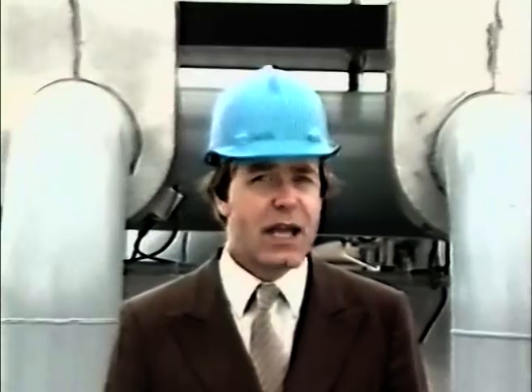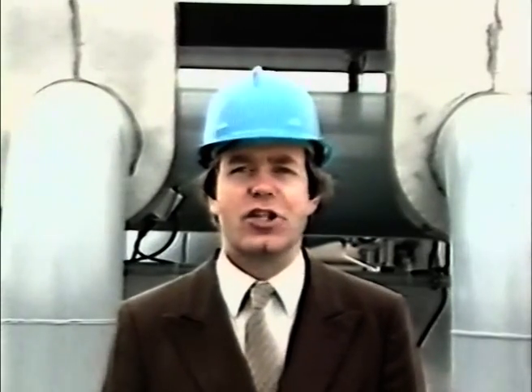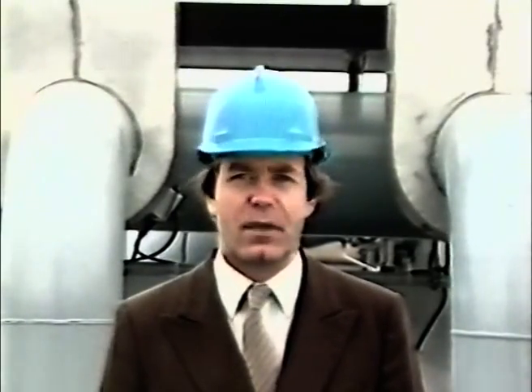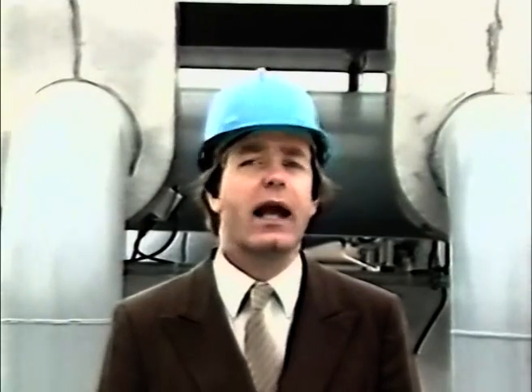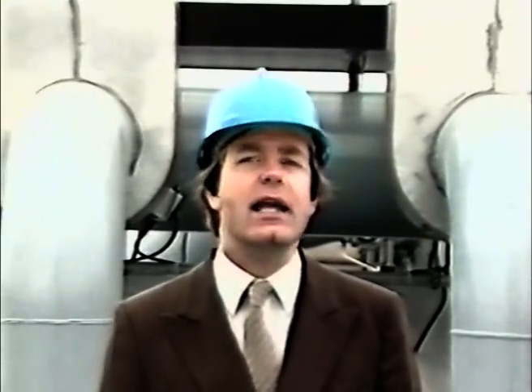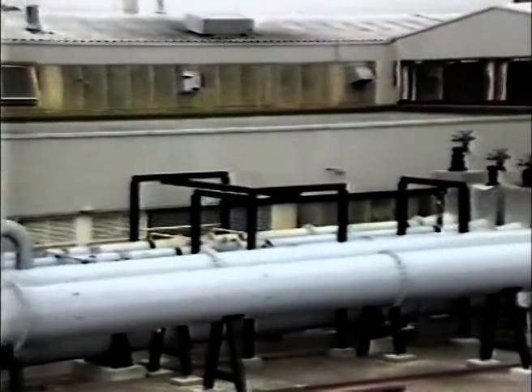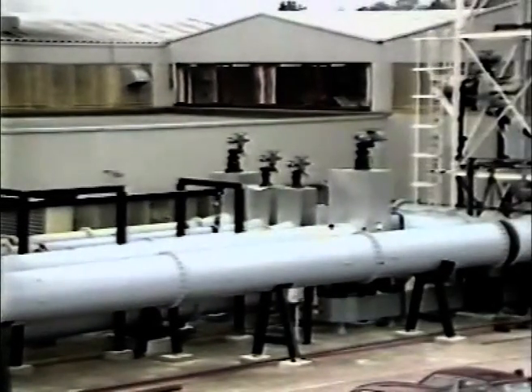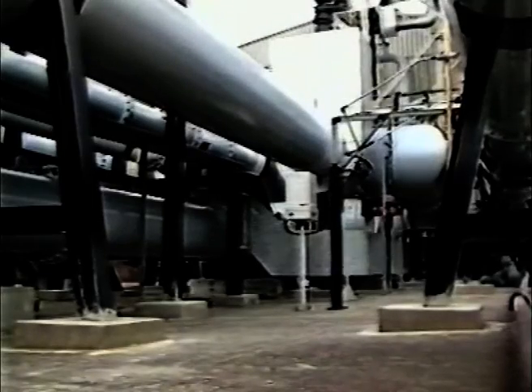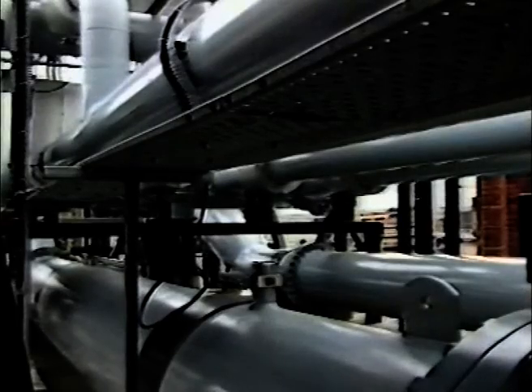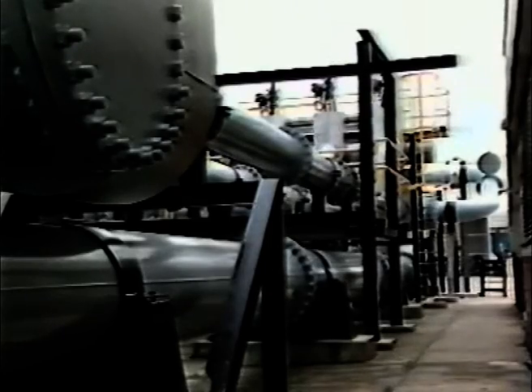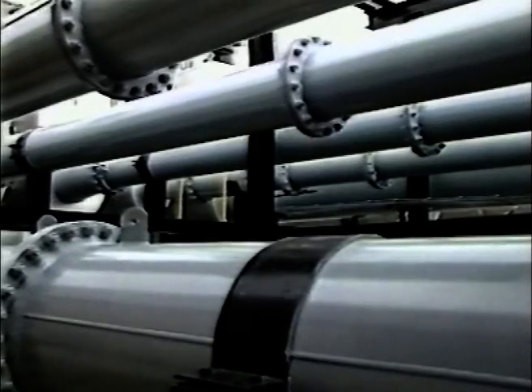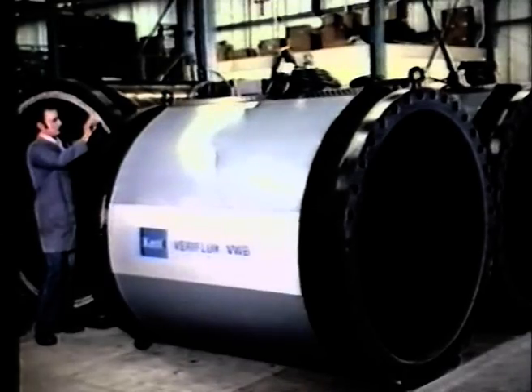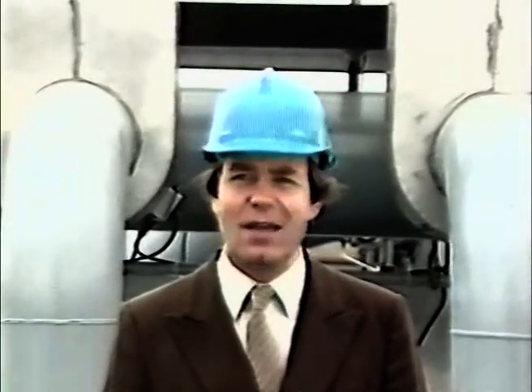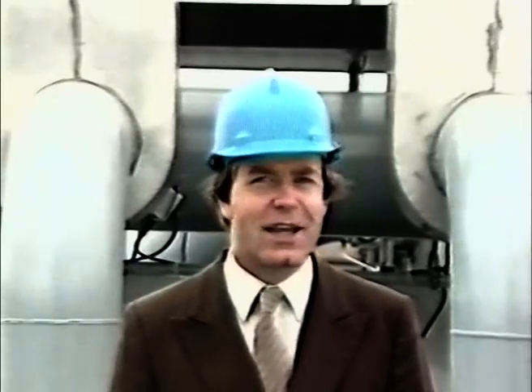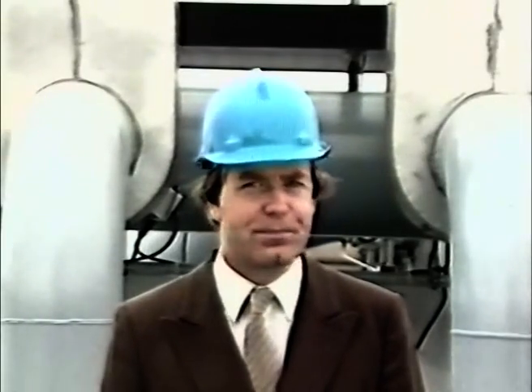industries. Because here, an entire factory and calibration rig have been custom built from scratch with the express purpose of manufacturing and testing flow meters to the highest possible standards. In fact, this is one of the world's largest calibration and test facilities for flow meters and control valves. And what makes it particularly important is its ability to run continuous tests. Continuous tests on meters and valves up to 2 meters in diameter. So large, in fact, you could drive a car through them. And for testing on that scale, you certainly need a lot of water.